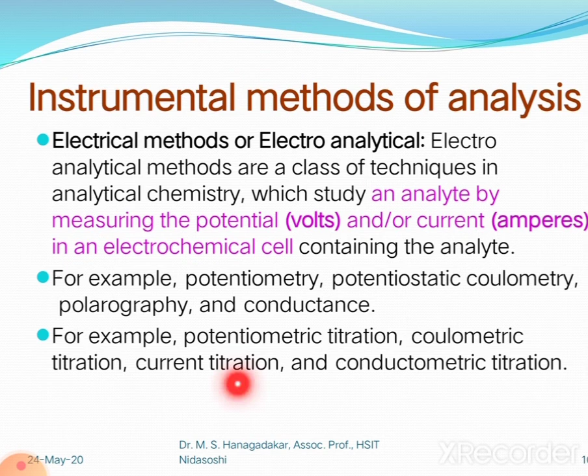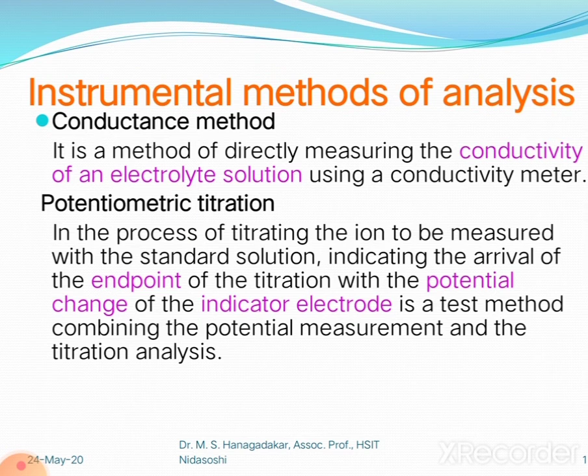So what is the conductance method? The conductance method is the measuring of the conductivity of the electrolyte solution by using an instrument called a conductivity meter. Whereas the potentiometric method is the process of titrating the ions to be measured with a standard solution, indicating the arrival of the end point of the titration by the change in potential, using a particular electrode, the indicator electrode. It is a test method combined with potential measurement using a reference electrode in the titration analysis.